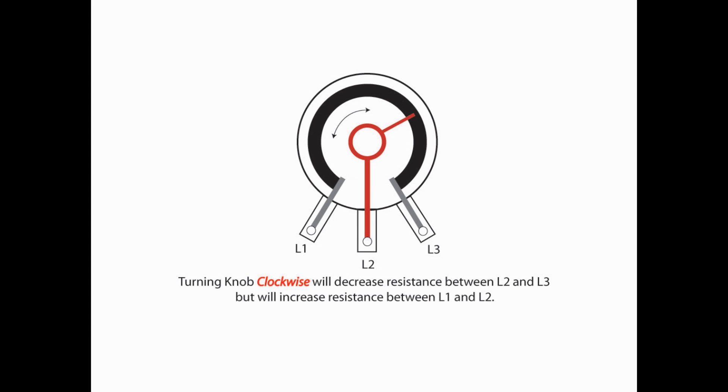Now, turning the knob clockwise is going to decrease the resistance between L2 and L3, but it's going to increase the resistance between L1 and L2. Conversely, turning the knob counterclockwise is going to increase the resistance between L2 and L3, but will decrease the resistance between L1 and L2. So again, remember, no matter how you turn that knob, your resistance between L1 and L3 is the same.